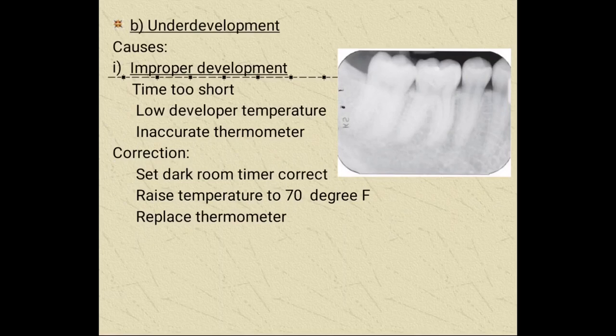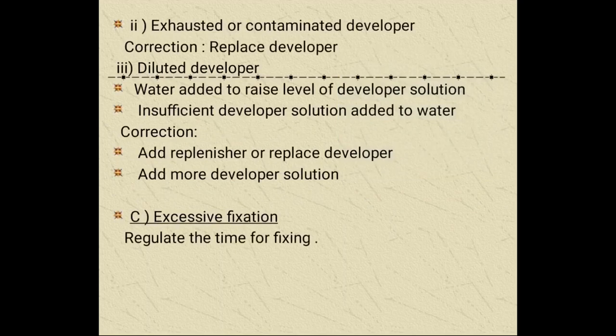Under-development causes include keeping the film too short a time in developer solution, low developer temperature, or an inaccurate thermometer. We can correct it by setting the darkroom timer correctly and raising the temperature to 70 degrees Fahrenheit, and replacing the thermometer. An exhausted or contaminated developer should be replaced. A diluted developer — where water was added to raise the level — requires adding replenisher or replacing developer. Excessive fixation requires regulating the time for fixing.